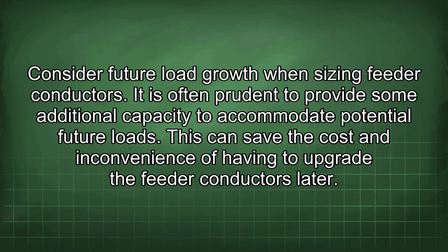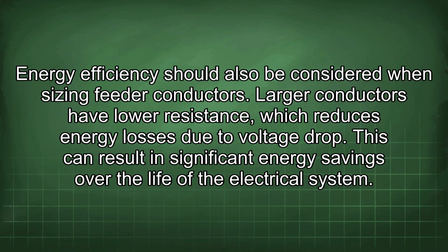Consider future load growth when sizing feeder conductors. It is often prudent to provide some additional capacity to accommodate potential future loads. This can save the cost and inconvenience of having to upgrade the feeder conductors later. Energy efficiency should also be considered when sizing feeder conductors. Larger conductors have lower resistance, which reduces energy losses due to voltage drop. This can result in significant energy savings over the life of the electrical system.